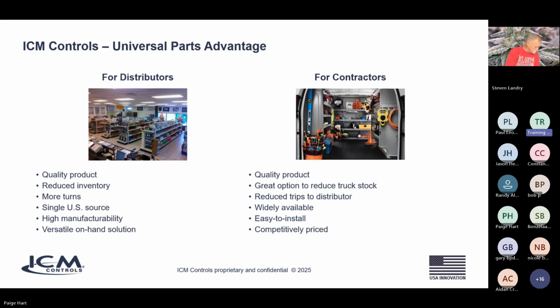For the contractors, it's a quality product again, but you're also going to reduce your truck stock. You don't have to now have multiple SKUs for the same product. You can reduce your trips back and forth to the distributor because you've got universal input voltage, universal reversing valve inputs, universal control voltage. So the refrigeration guys don't have to worry about picking a special unit that's only for line voltage reversing valves. It's all universal now. So it makes it much easier for contractors to pick one product, put it on their truck, less back and forth trips, makes the repair time a lot quicker.